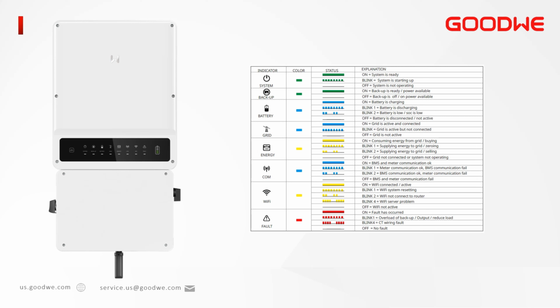Once you have completed the wiring to the inverter, the next step is to start the commissioning. Note that the inverter only has LED indicators. All configuration and monitoring will be done via the apps. In case you have a question on the LEDs, this table is included in the manual. Additionally, on the left side of the inverter, you will find a label with this information.